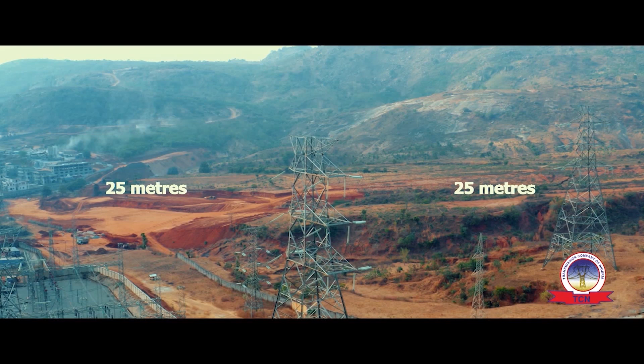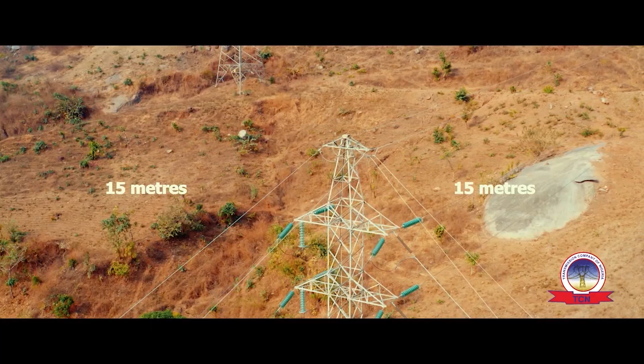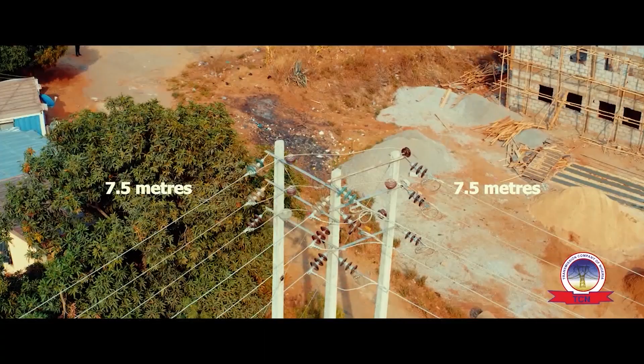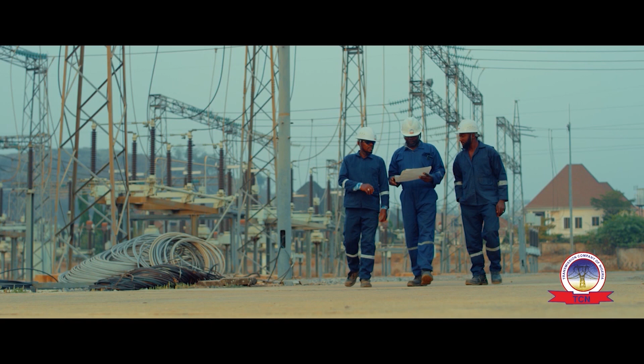Safety compliance means that before erecting any structure around an electricity tower or line, there are safety distances you must adhere to: 25 meters on both sides for a 330 kV tower, 15 meters on both sides for a 132 kV tower, and 7.5 meters on both sides for a 33/11 kV tower. These stipulated safety distances are what we call right of way. If these basic safety distances are adhered to, there will be less loss of property and lives from cut transmission lines.